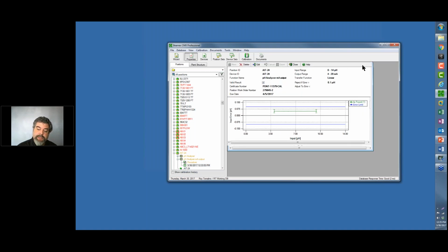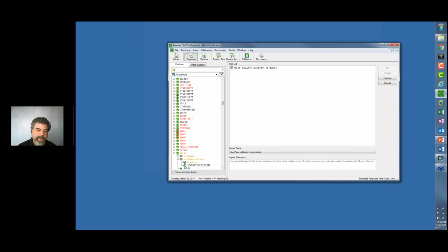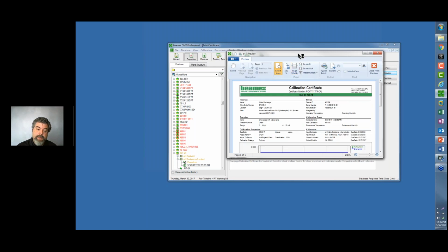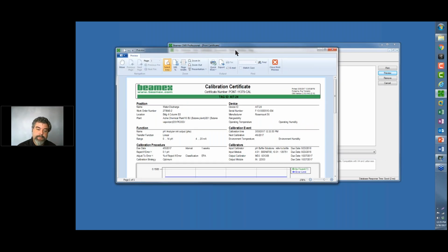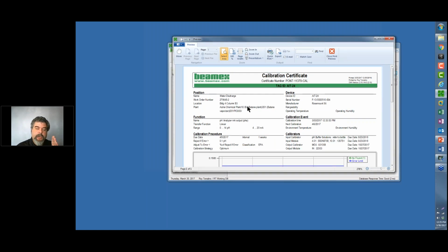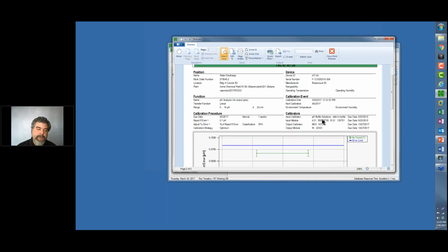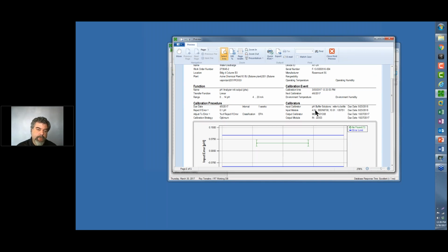Right here is our test result. Let me bring up a calibration certificate, because that's the way I would want to view this information. So I'll preview it. Let me zoom in here. The certificate itself has all of our information, and this is what makes it traceable all the way up to the top, the national laboratories or the national standards. If I scroll down under calibrators, here's where I show my pH buffer solution, and I say refer to bottle. The different bottles are my 4 and my 10. And I've got the lot numbers, including due dates. My due dates are essentially when the bottle says that it expires. And then the output is my MC6 calibrator, which was measuring the current on the output.